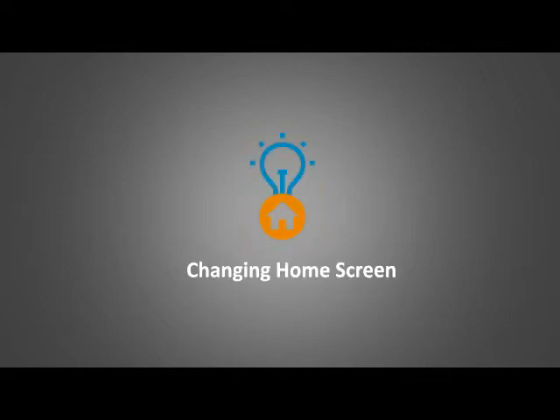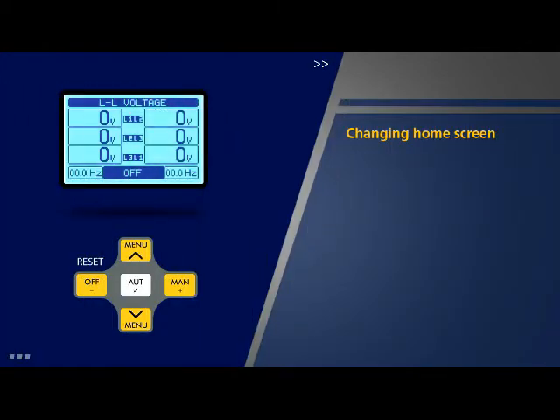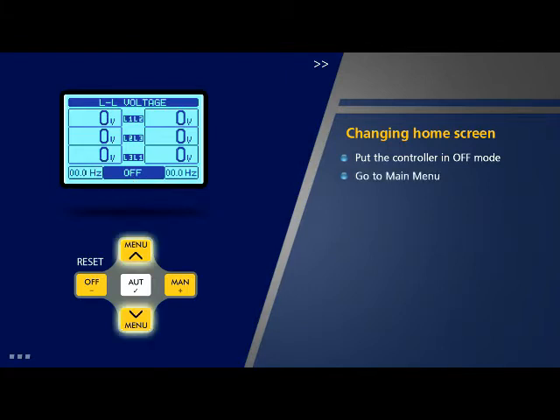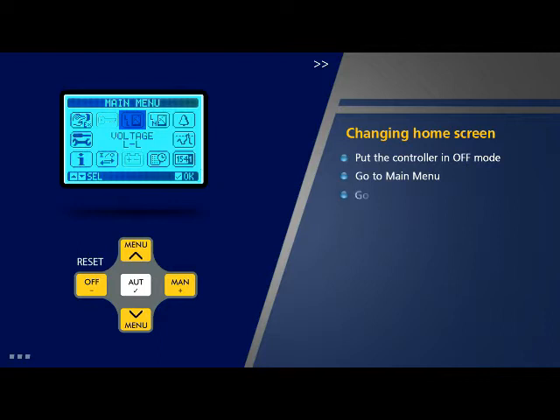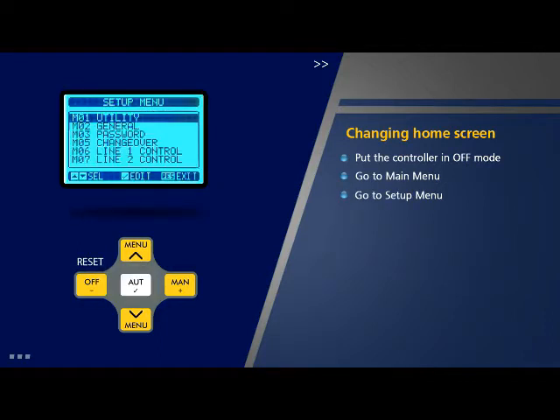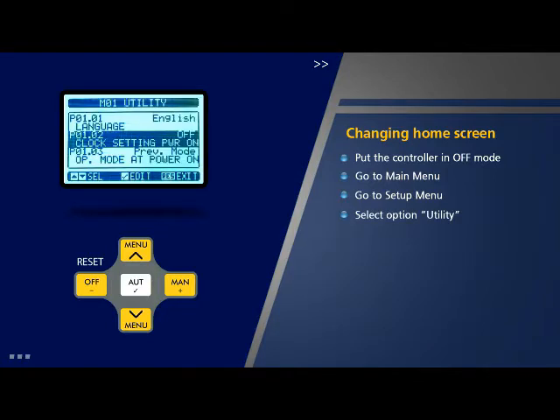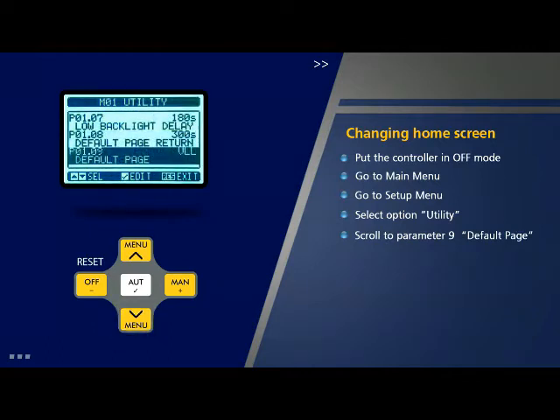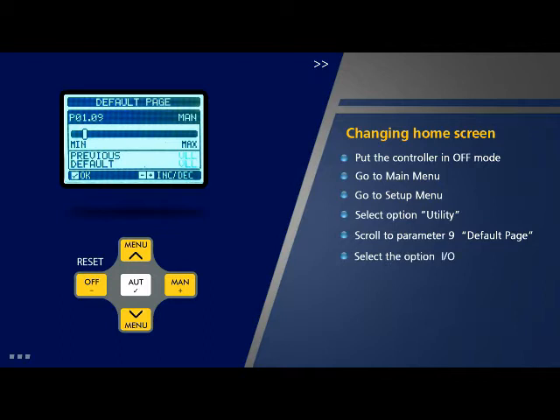Changing home screen: Put the controller in off mode. Go to main menu, scroll using plus/minus keys to go to setup menu and press OK. Select the option 'Utility' and press OK. Scroll down to parameter 9 which is default page and press OK. Select the option to be chosen as default, for example 'Input Output', and press OK.